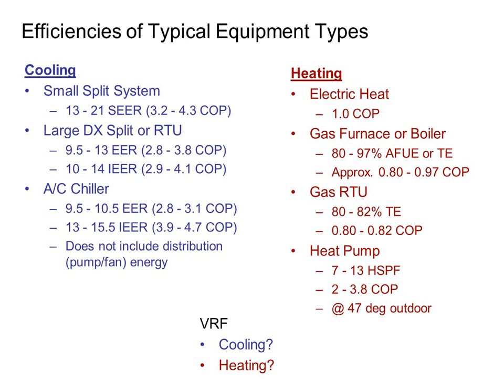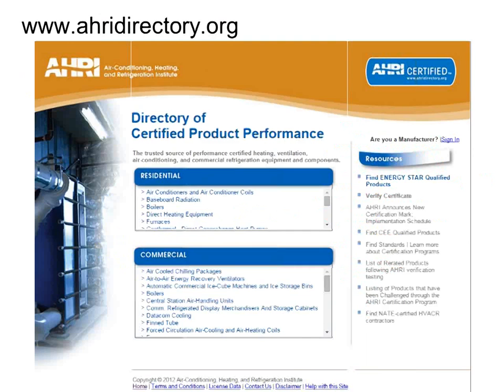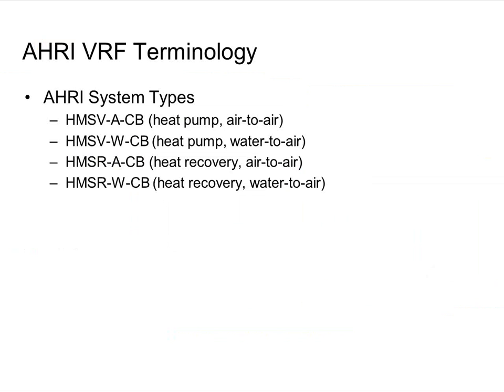Natural gas is super, super low price. So a lot of times a gas heating system like a boiler will beat out a heat pump in cost. That's true usually when you have heat pumps that are fixed speed. Now that we have variable speed heat pumps, residentially and with commercial VRF, that's not always true anymore. But this particular example here was specifically based on energy. And energy and cost are two things that are not the same.